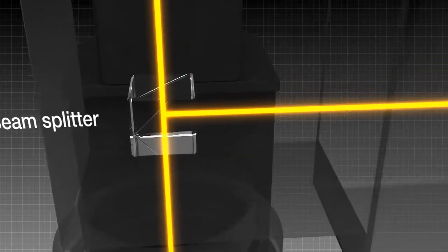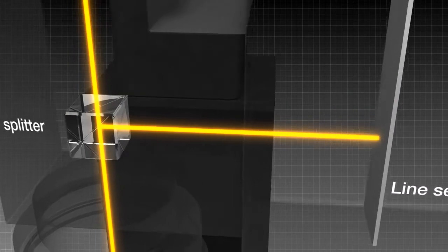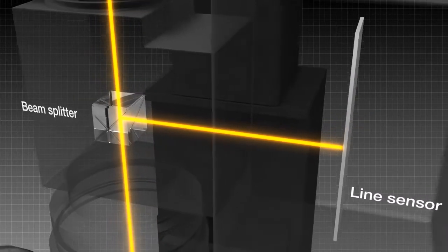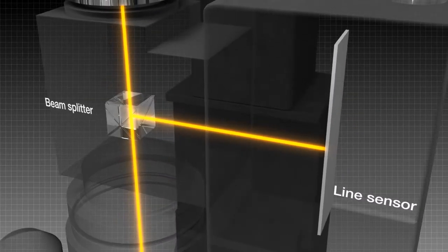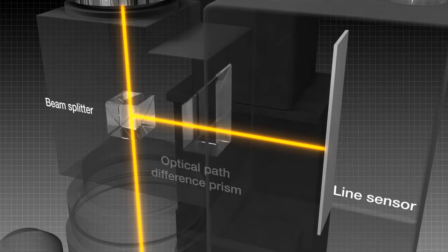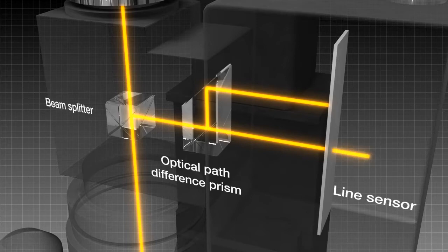At this point, the line sensor is only being fed one signal, so it cannot determine whether the focus point is high or low. An optical path difference prism is placed in front of the line sensor, and the line sensor now receives signals from two points.